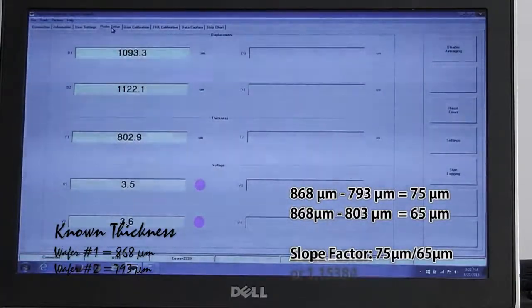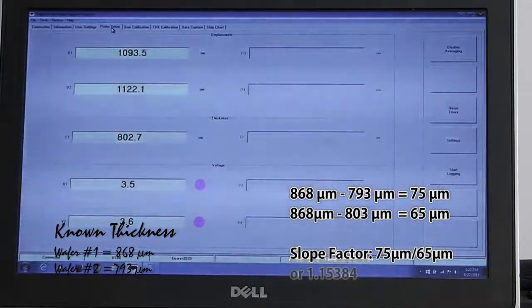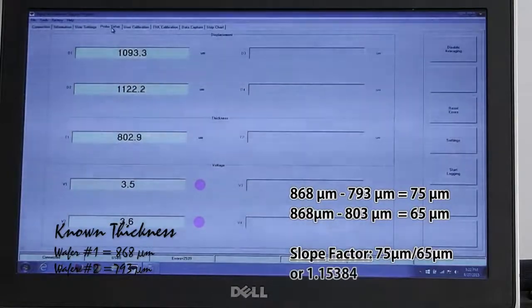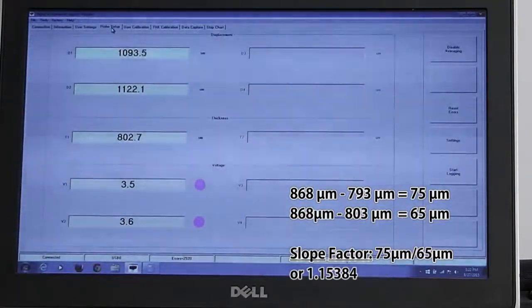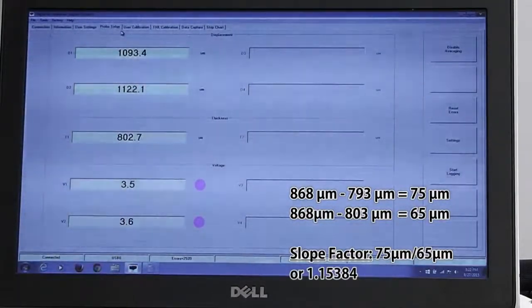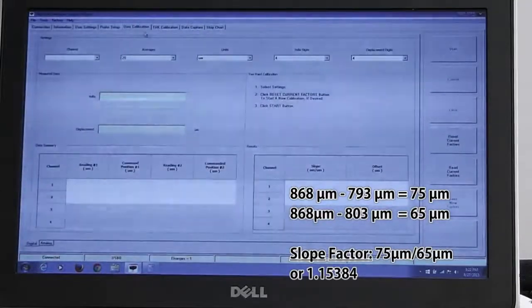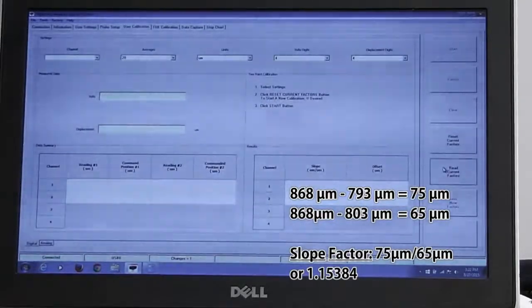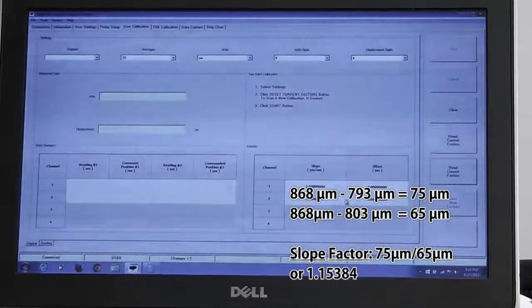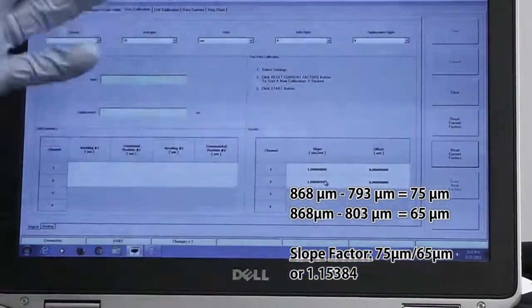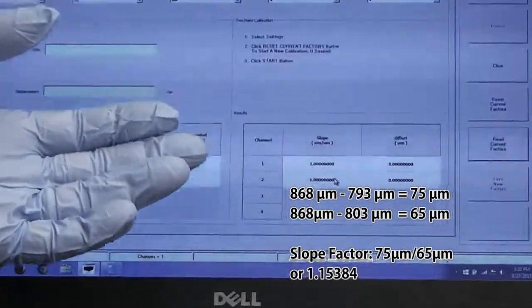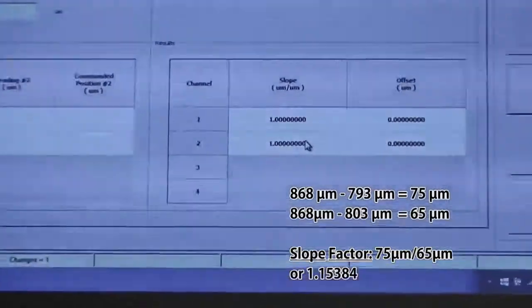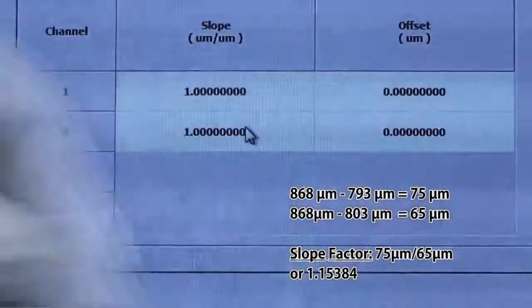In this case, I've already done that and we know that the slope factor for sapphire is 1.15384. So the next thing we're going to do is we're going to go to user calibration window. We're going to read the current slope factor which is 1 from our original calibration when the unit was calibrated at MTI. And our slope and offset is 1 and 0.